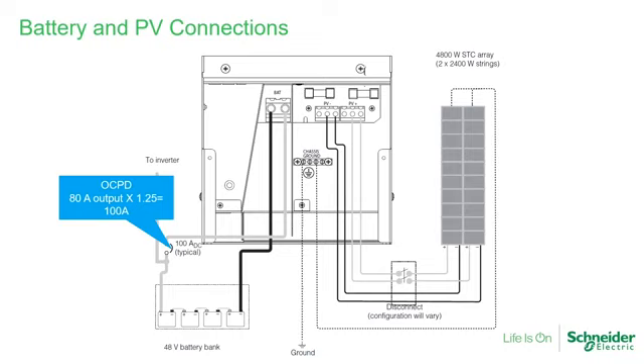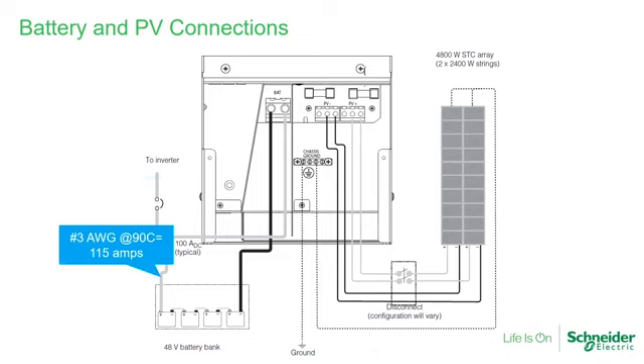So why are we recommending a 100 amp DC breaker? It's because the output of this unit is 80 amps, and we need to multiply that by the safety factor of 1.25, which puts us at 100 amps. Caution here: if you have a 100 amp breaker, you have to make sure that the conductor can carry the current, because the job of the breaker is to protect the conductor, not to protect the solar charge controller or the inverter. Per code, the breaker needs to be 100 amps, so the conductor ampacity needs to match the breaker.